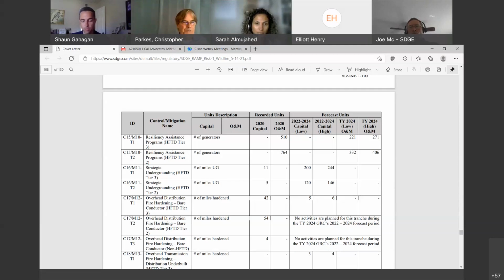If you were using the new program of covered conductor or insulated conductor, whatever you want to call it, you'd probably more likely than not be replacing the poles as well - is that fair to say because of the added weight of the covered conductor? That's fair, it does depend. We do the calculations to make sure we're not replacing things we don't need to. If there are existing steel poles that can support the weight of the covered conductor, we'll leave them in place, assuming they pass our loading calculations. But yes, if there are older poles not designed for that, it's very likely they'll be replaced.